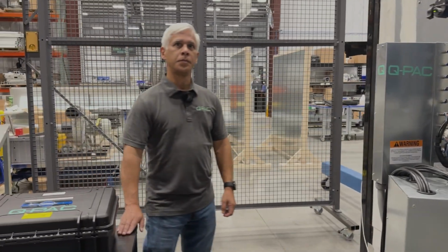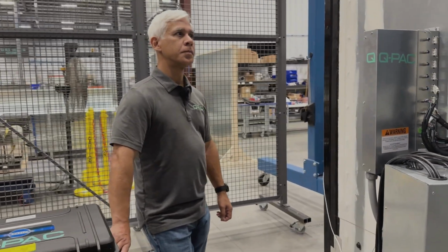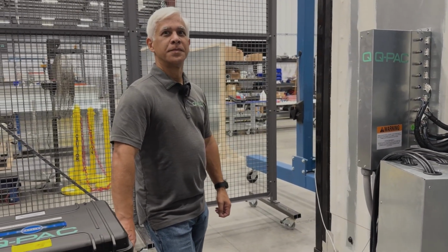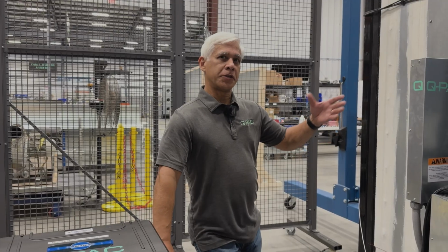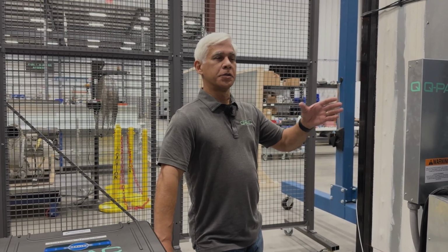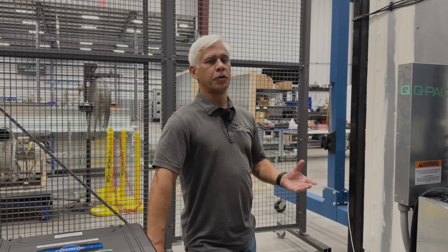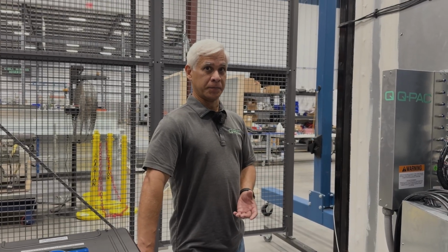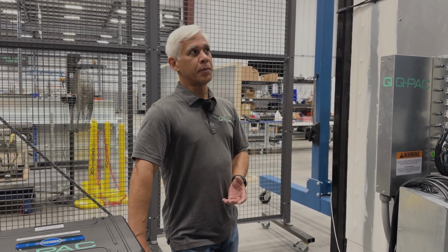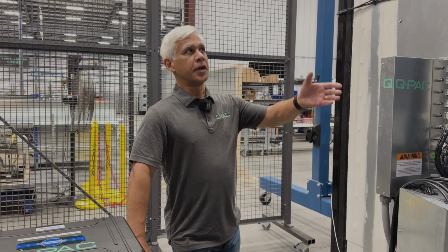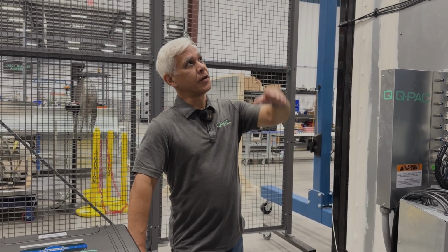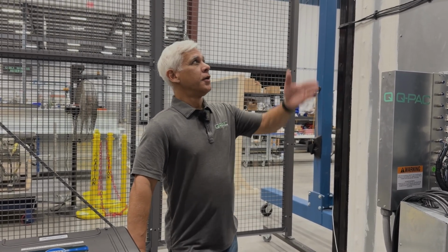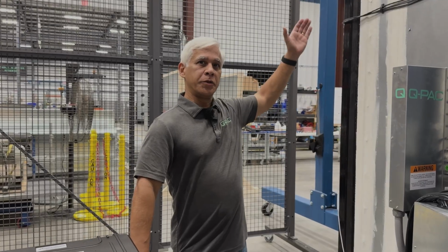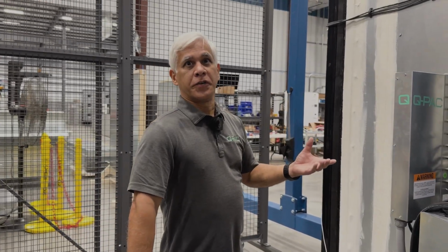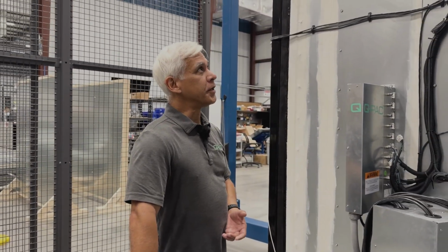Cool, and just a general kind of stupid question, why is it important to measure so many things when it comes to airflow in a commercial setting? The fan manufacturers have characterized their individual fans and motor combinations really well. We know the performance of a single fan. The industry really doesn't know what happens when you put 4 fans together in a spacing of what we have there, a fraction of a diameter, versus when they're spaced out a full diameter away from each other. So we use fudge factors, in a manner of speaking.